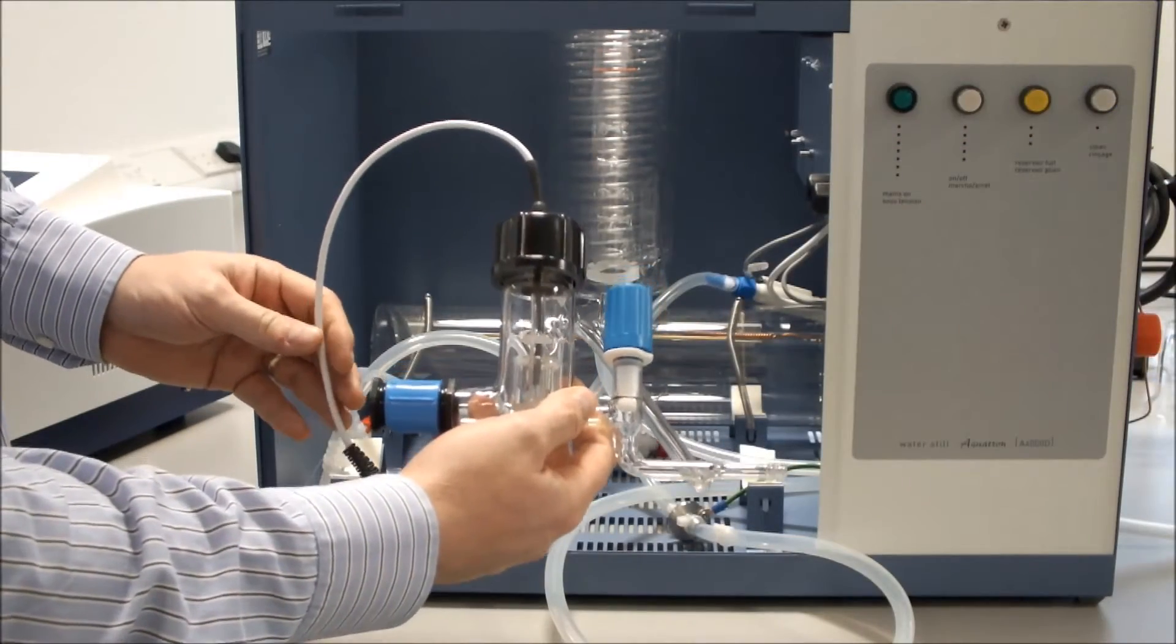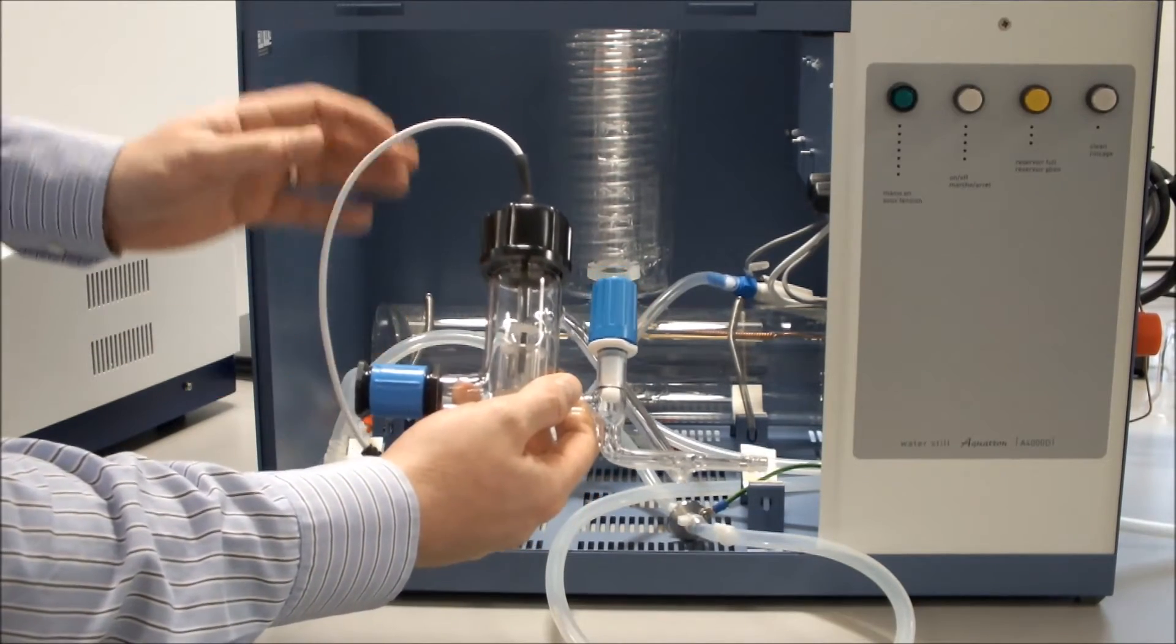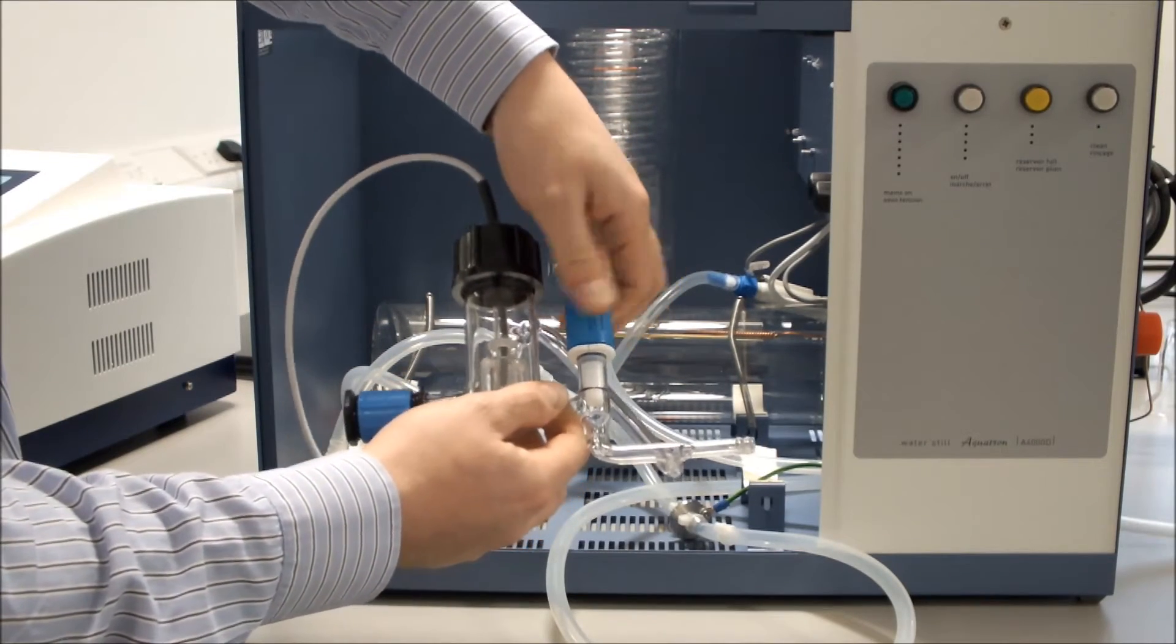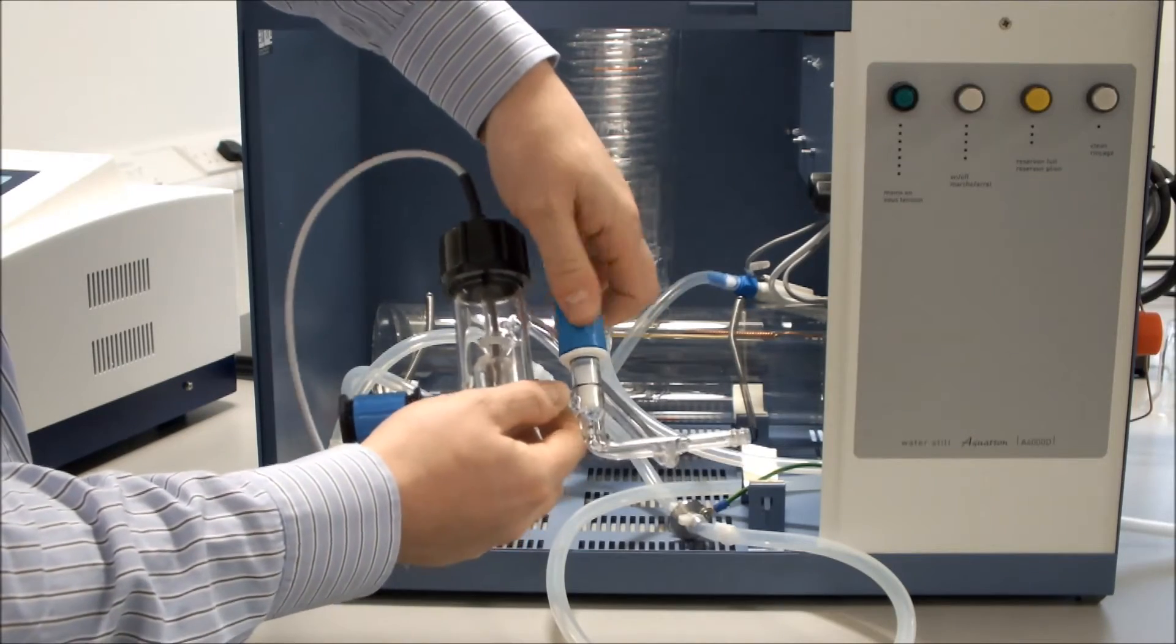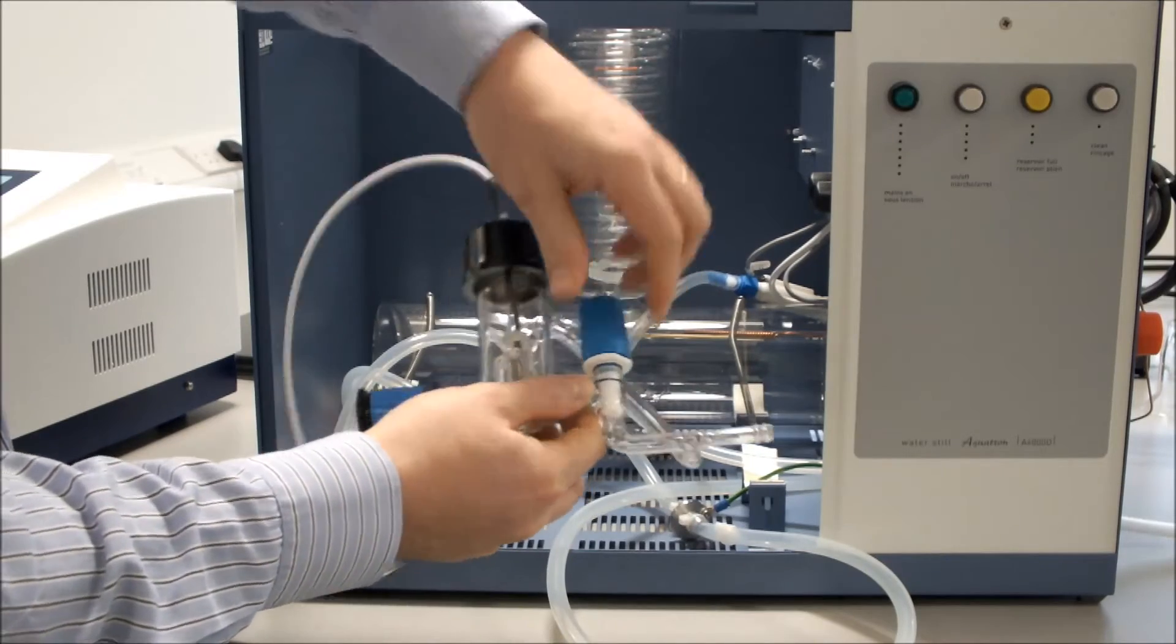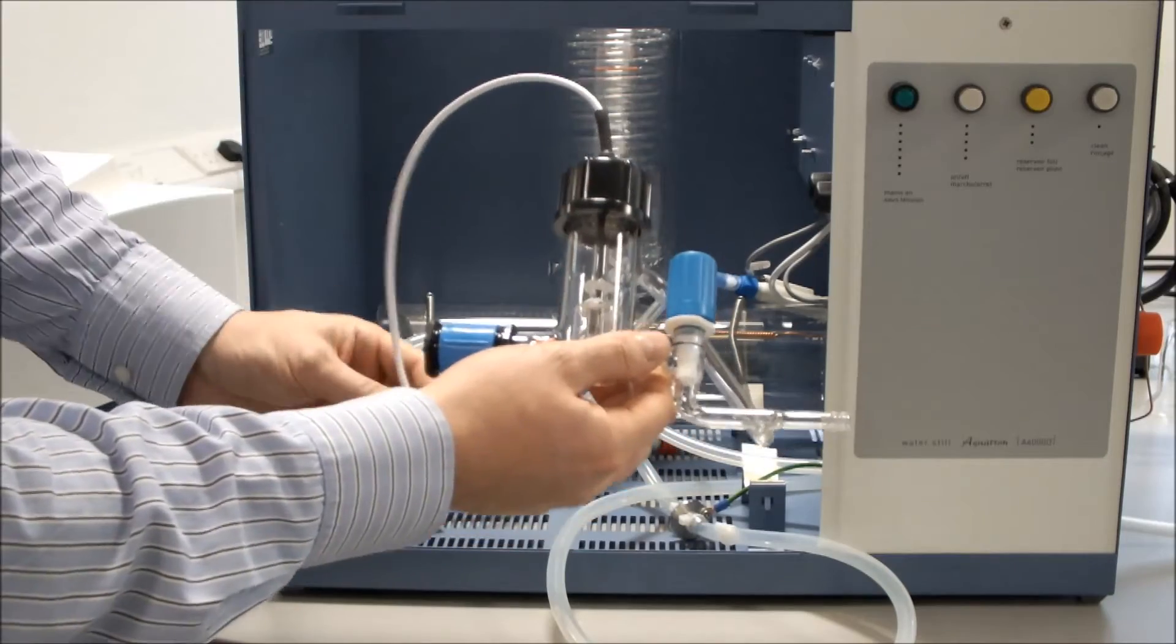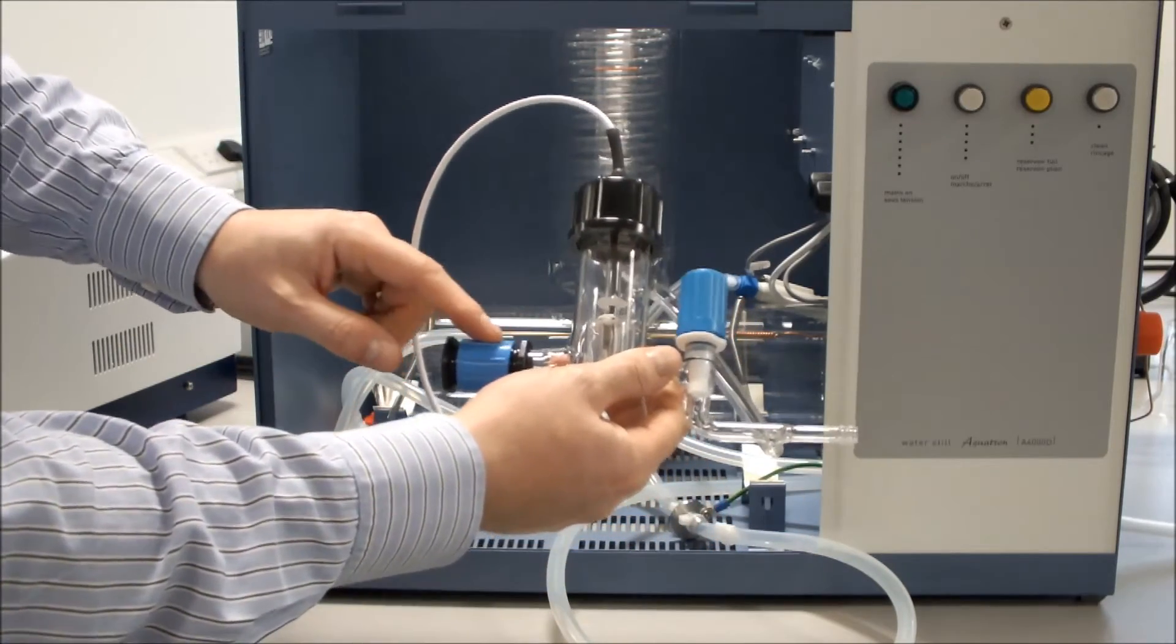One thing to do is to connect the rear boiler water level sensor. Now the sensor itself consists of a Rotaflo stopcock which should be fastened down so it's closed. Like so. In the tube itself is the actual float switch which is connected to an electrical connector.